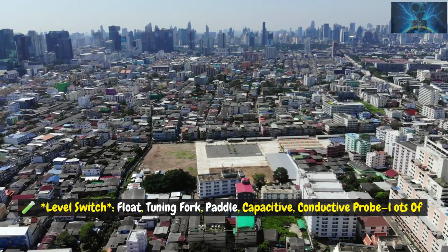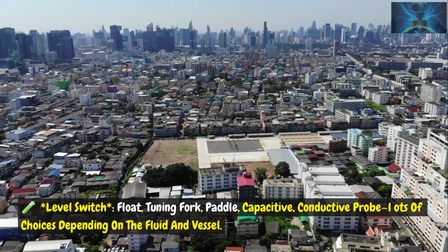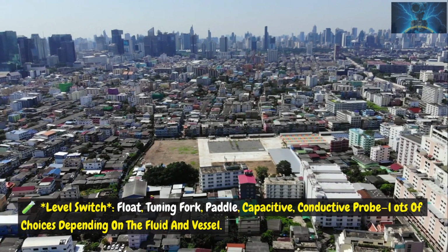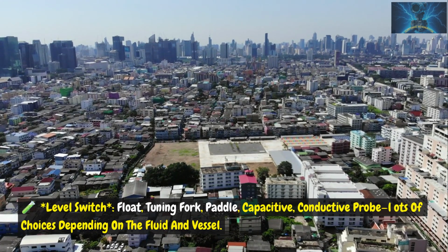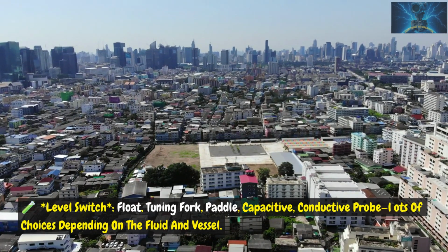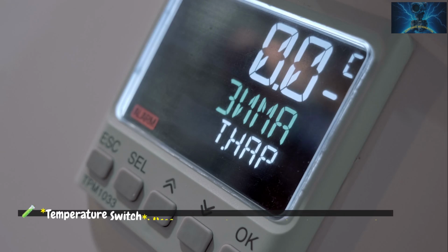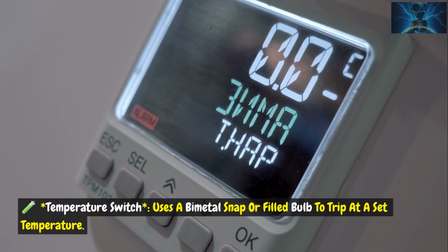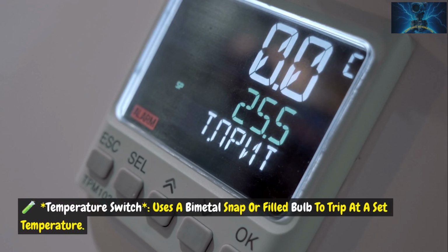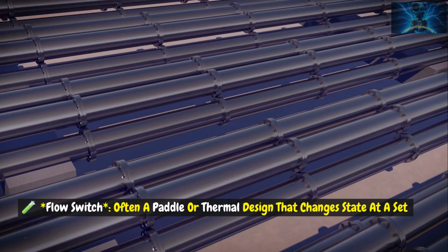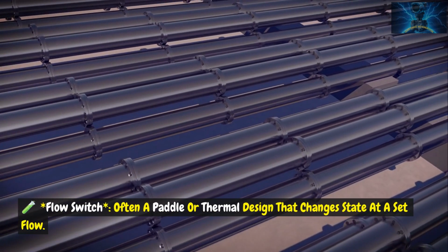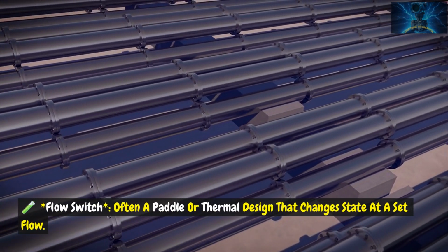Level switch: float, tuning fork, paddle, capacitive, conductive probe. Lots of choices depending on the fluid and vessel. Temperature switch: uses a bimetal snap or filled bulb to trip at a set temperature. Flow switch: often a paddle or thermal design that changes state at a set flow.